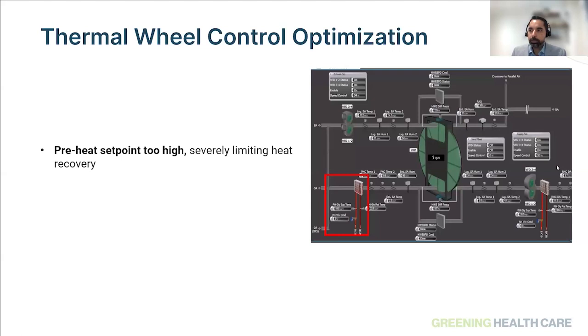Just a heads up, we'll be talking in more detail about thermal wheels control optimization in an upcoming webinar, which will get into details about some of the issues that we're documenting with thermal wheels operations. But the biggest one that we're currently seeing is a preheat set point that is too high. So in your facility, if you have a thermal wheel, I would recommend you go talk to your operations team and look at these perimeter preheat set points.